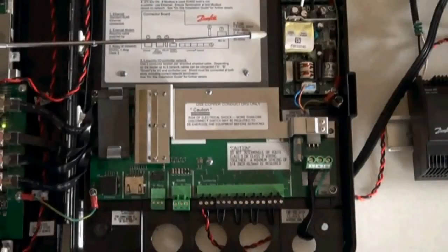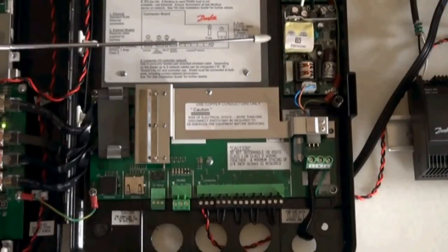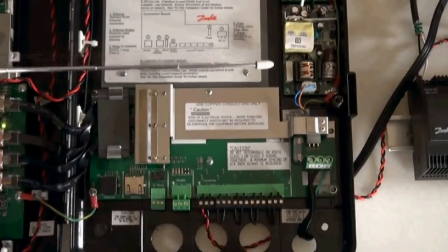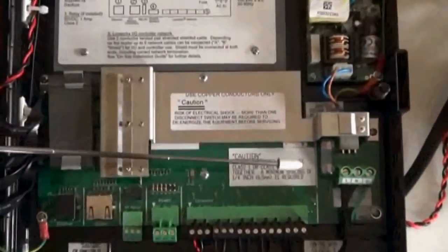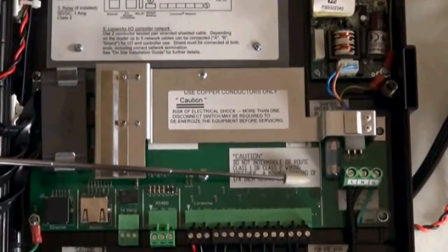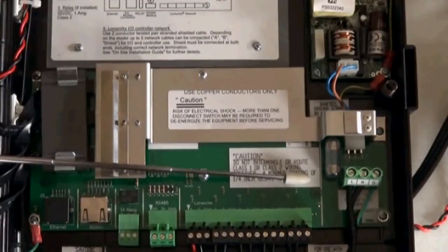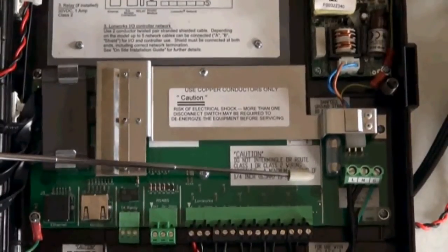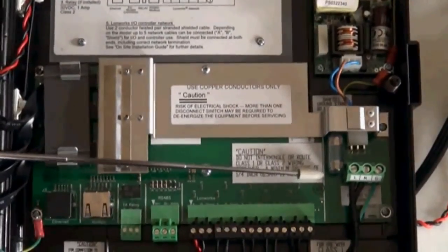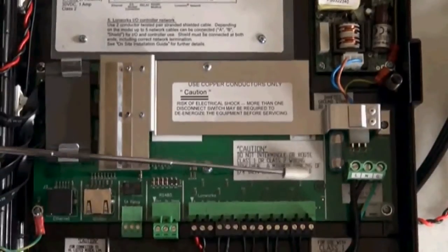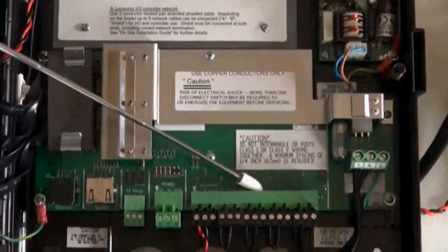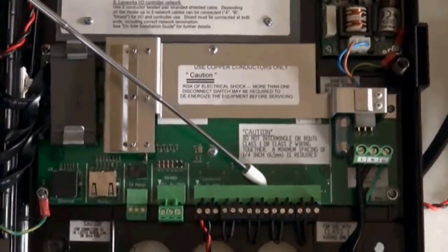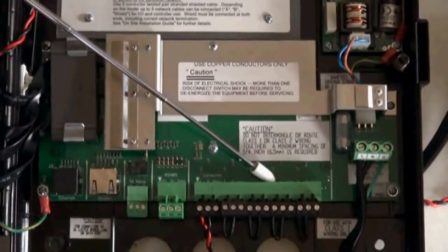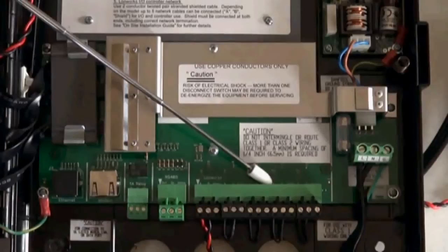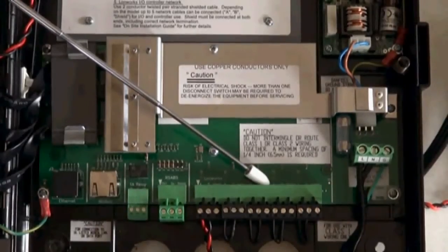The power supply board for the Danfoss AK2-55 is found here. Moving down through the controller, we see the incoming power, which can be any voltage from 100 to 240 volts AC. Next, we find 5 ports for I/O connections. These are Echelon based.